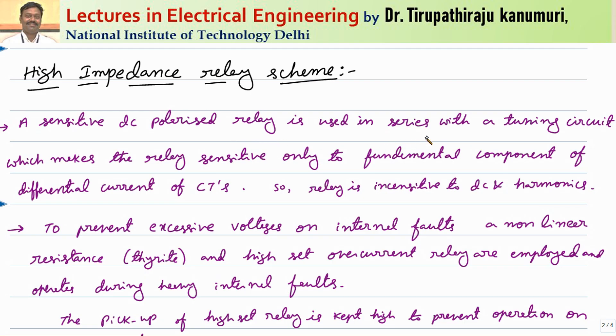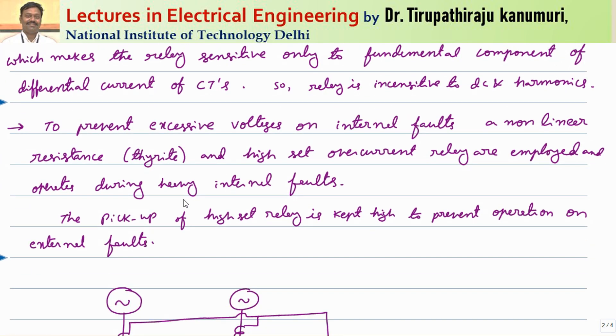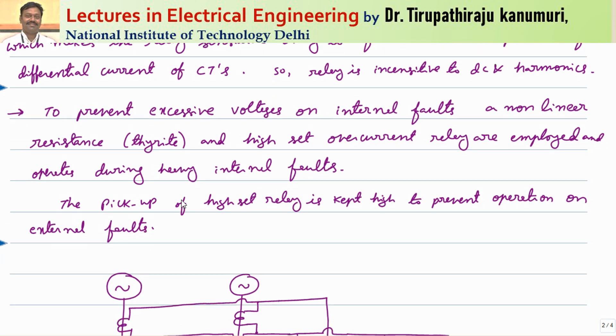The high impedance relay is connected in series with a tuning circuit. This tuning circuit will only allow the fundamental component and does not allow higher order harmonics. Particularly whenever a through fault causes CT saturation, higher order DC and harmonic components are produced. Those components are not allowed to pass through your relay — meaning it will only sense the case of internal faults and will not sense external faults or through faults.